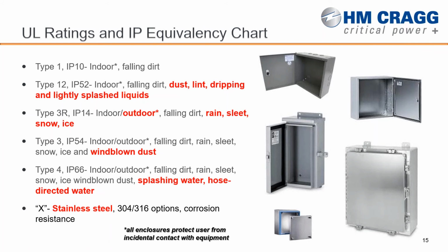The X is, in many cases, stainless steel, but what the X in the rating really means is corrosion resistance. So it could be 304 or 316 stainless steel, but it could also be a polycarbonate. It could also be aluminum. Any one of those three would qualify as X, but most people, when they say NEMA 4X, think stainless steel. And in many cases, that's what we default to as well, unless we have a conversation about weight or other specifics for your project where we might want to offer one of the other options.